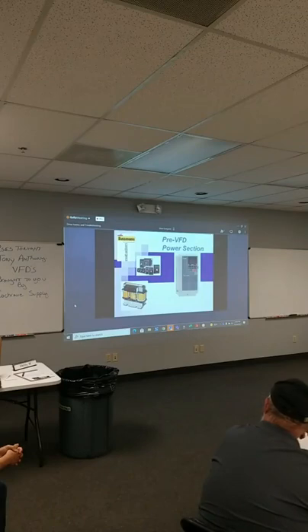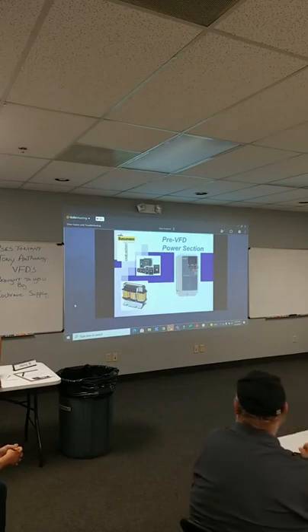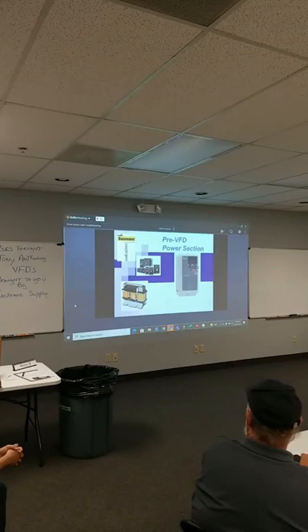So basically, there's three sections of a drive. If you kind of look at it, there's what is before the drive, how we can feed the drive and protect the drive, the pre-VFD section. Then there's the VFD section. And then we've got after the VFD, between the VFD and the motor. So we'll start with the pre-VFD section. I know most of you are probably more technical. I'm going to go through some of this, it's pretty simple, and we'll go through it quickly. Some of the others we'll cover in a little bit more detail.